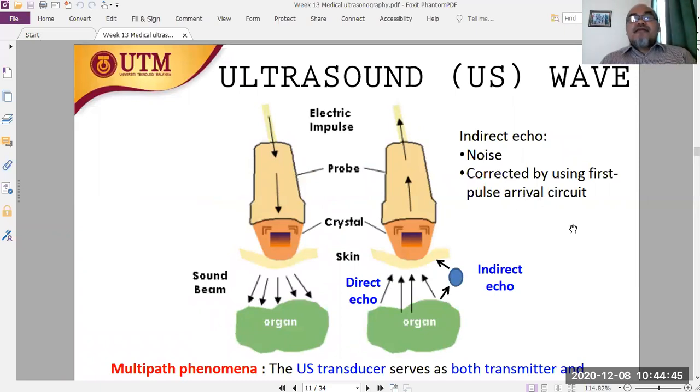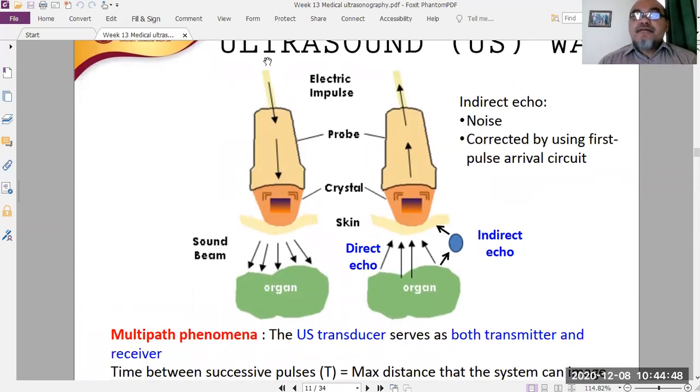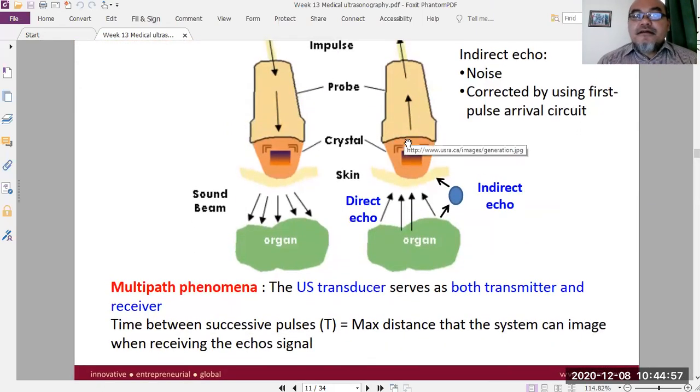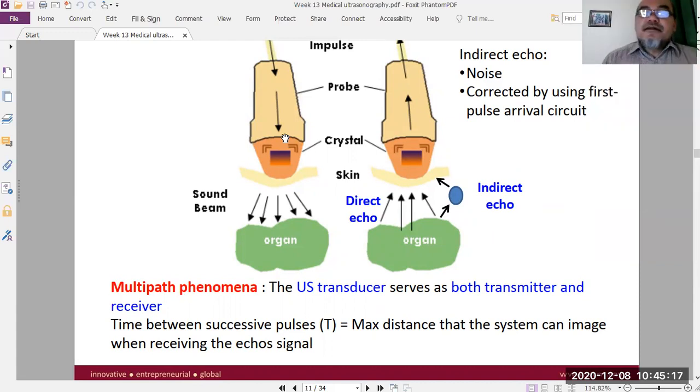So in ultrasound, an electric impulse is given by the electronics to the transducer, the probe, what we call the probe. The probe itself has an ultrasonic piezoelectric transducer, a crystal. It could be PZT.